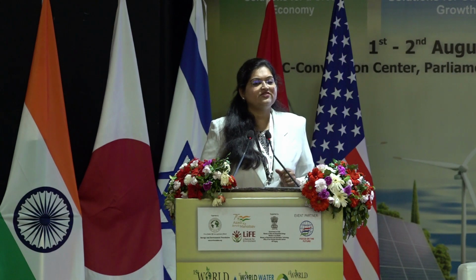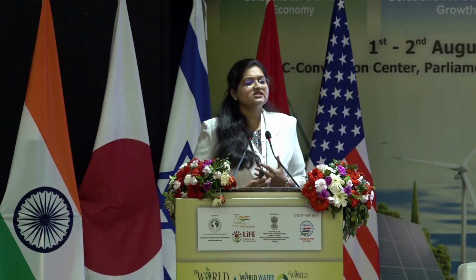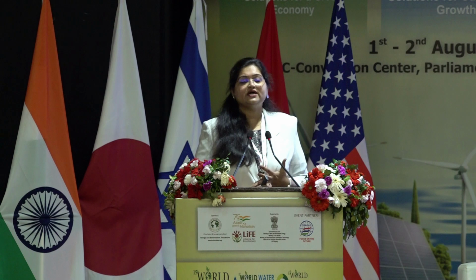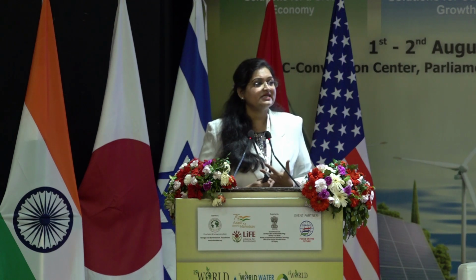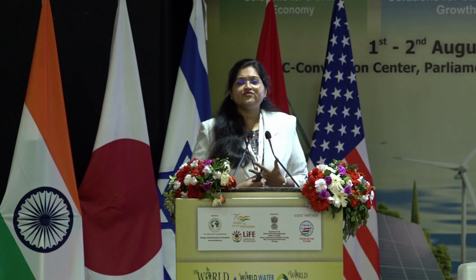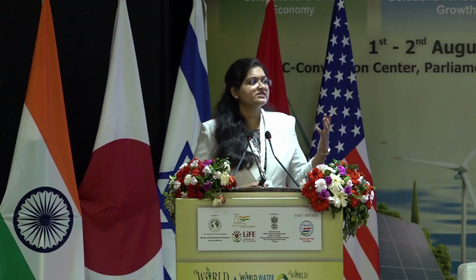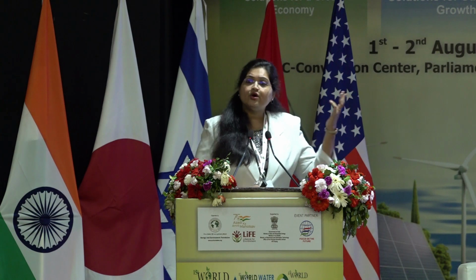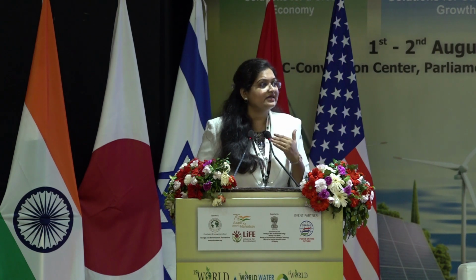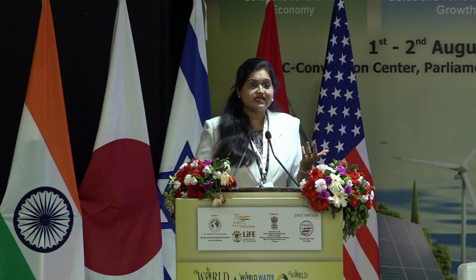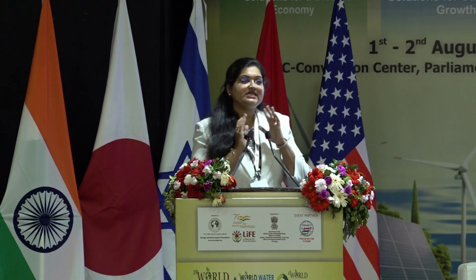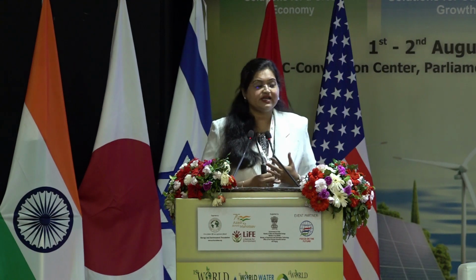There are different kinds of applications, and this is a very important part where we are working on anti-islanding detection. When we talk of microgrids, you might have one connected to the grid, or operating in an islanded condition for which it's designed - in case there's something wrong with the grid, it isolates itself but keeps the other part of the network alive.